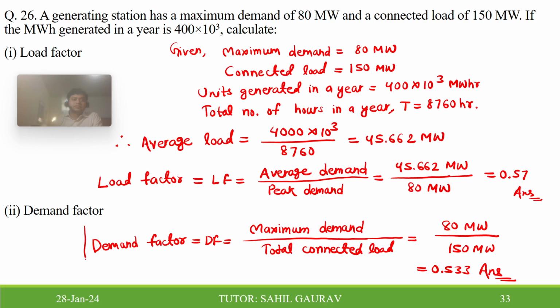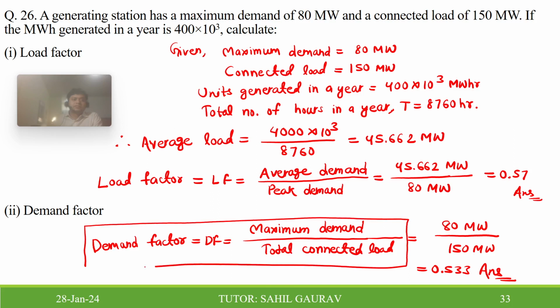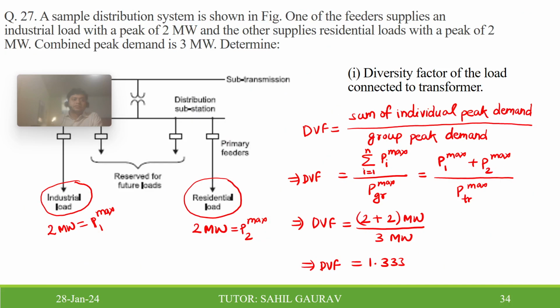Now for the demand factor, it is the ratio of maximum demand to total connected load. Maximum demand is given as 80 megawatt, and total connected load is also given, so the demand factor is quite easy to calculate. Both values are given directly, but for the load factor they generally give the values in terms of energy consumption or energy demand. So just calculate in terms of power and then get the load factor value. So the demand factor you will get is 0.533. Now the next problem.